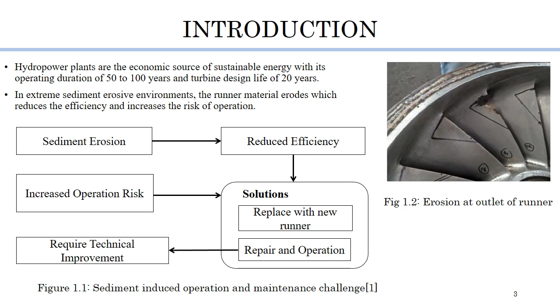As you can see in the figure below, the ultimate solution is to maintain the efficiency and decrease the risks of operation, either by replacing the eroded runner with a new one or by repair and operation of the old one. Replacing the eroded runner will be much costlier, so welding repair of the damaged runner is preferred due to low cost, as well as it does not impair the metal property if carried out properly. Therefore, welding repair is chosen as the best alternative in hydropower plants in Nepal.